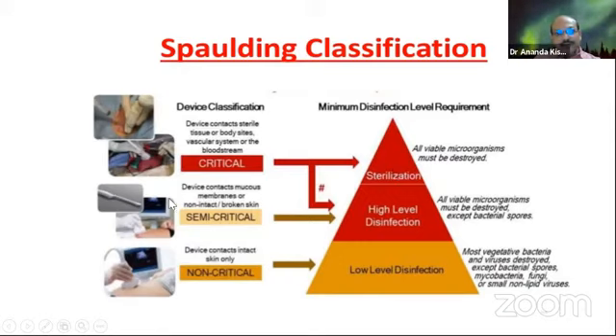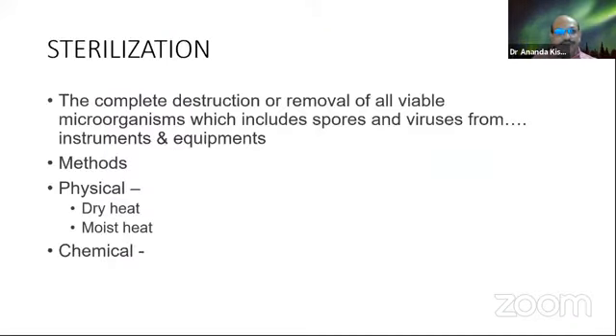The semi-critical, the conditions where implants are used, should be treated with a high level of disinfection, where all viable microorganisms must be destroyed except the bacterial spores, whereas the instrument used for the non-critical condition requires a low level disinfection, where most vegetative bacteria and viruses should be destroyed except the bacterial spores, mycobacteria, fungi, and the small non-lipid viruses.